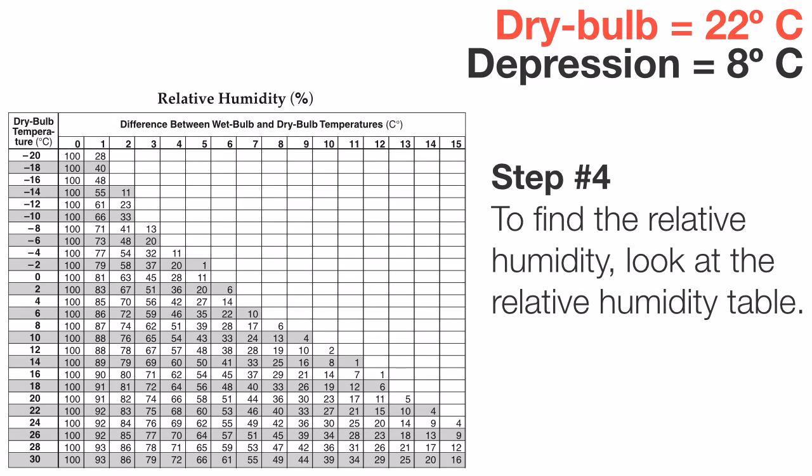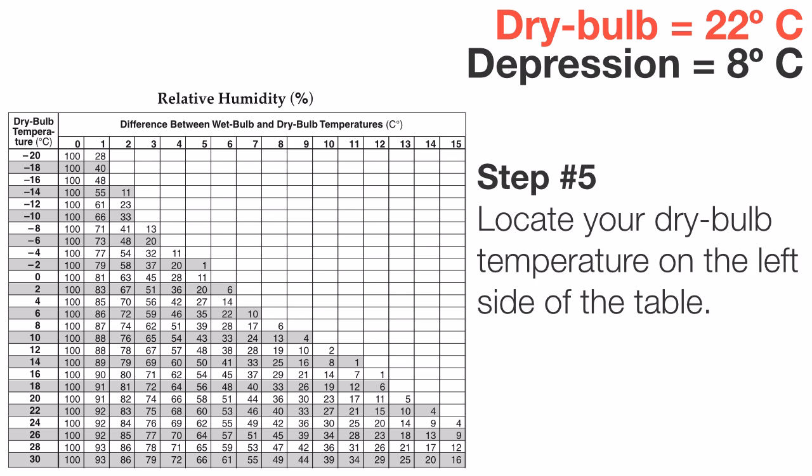Like I said, we'll start with the humidity. So we need to look at our humidity chart and what we're going to do is we're going to begin by looking at the left hand column on this chart where it says dry bulb temperature. Our dry bulb is 22 degrees Celsius, so we're going to locate that on the left and just kind of mark off that row as I did in green here.